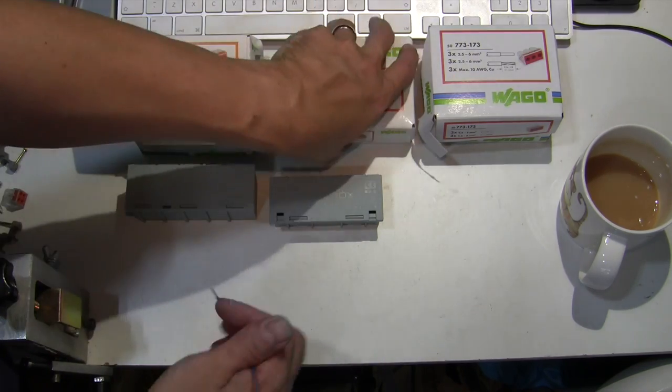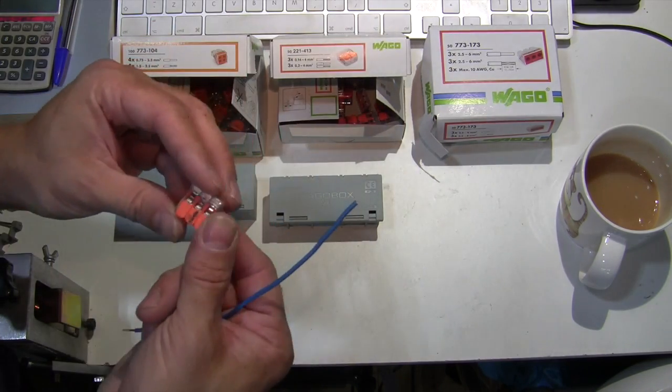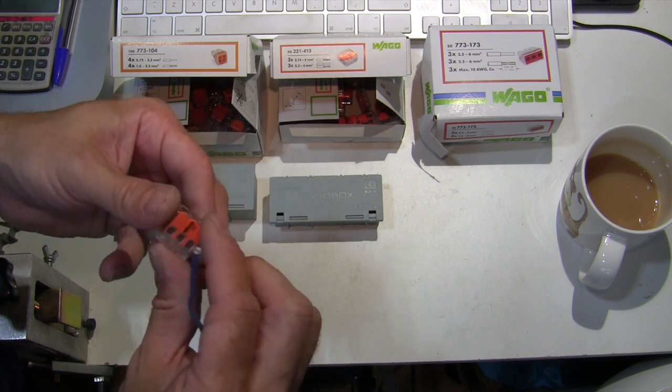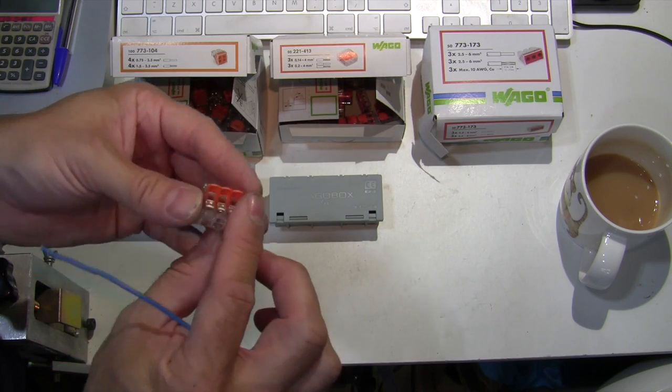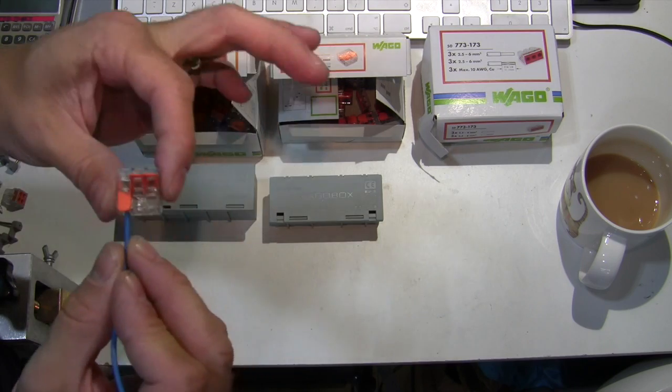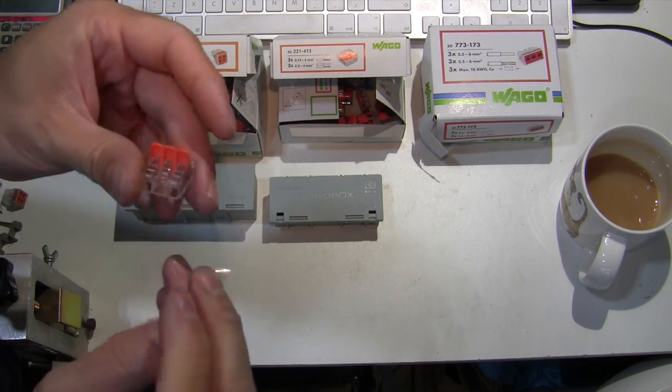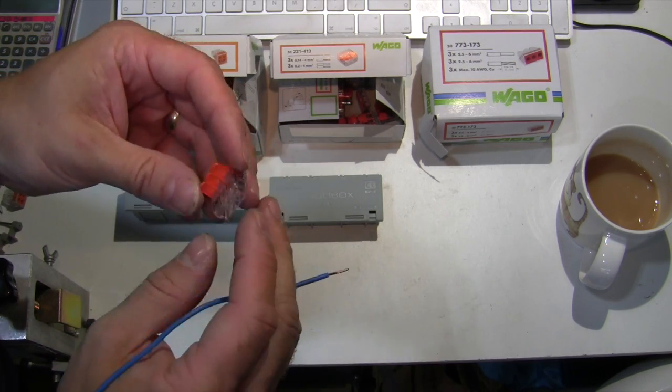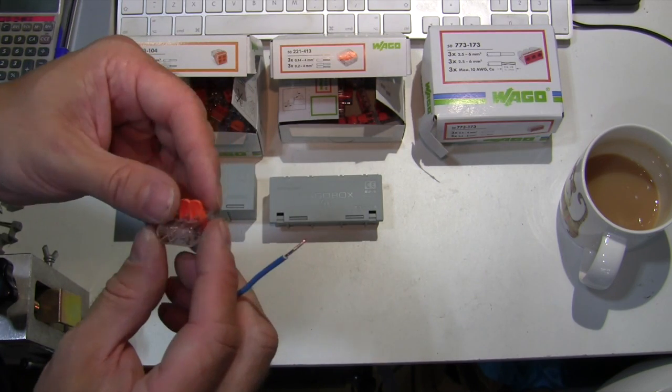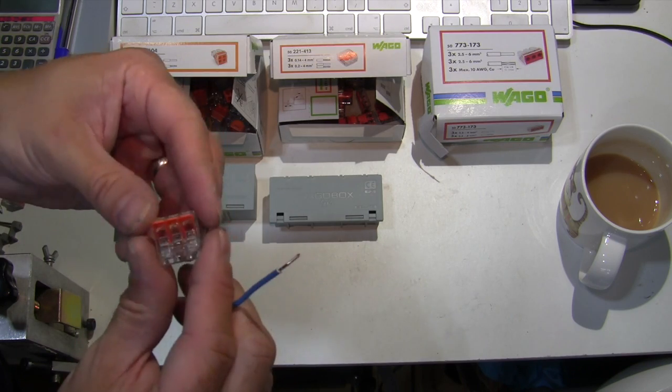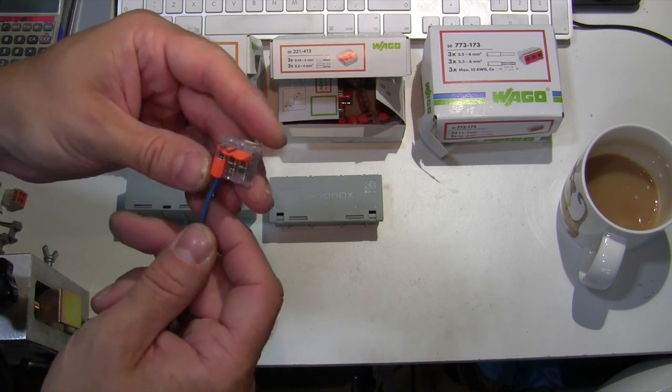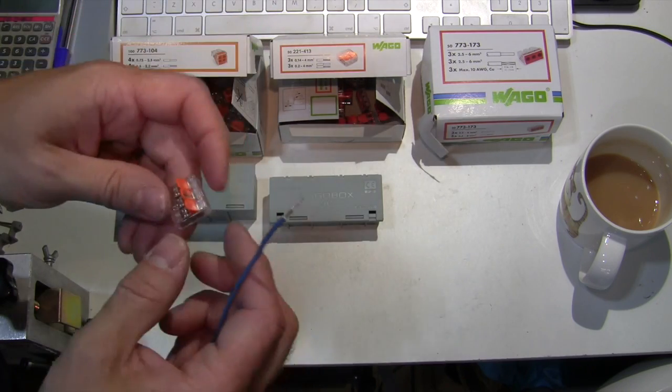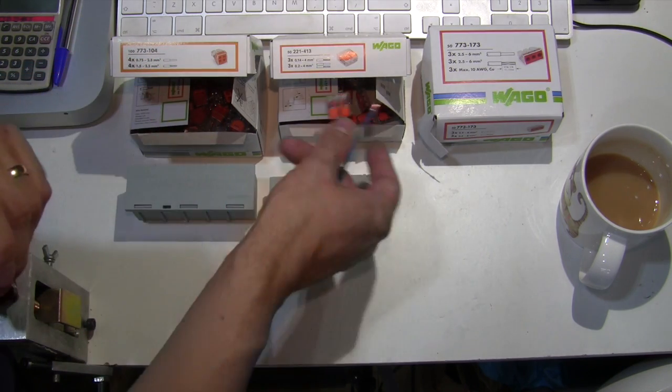And if you don't want to go for that sort of connector, they do a lever type as well. I like the 221 series here, which is the slightly more expensive, but it's the clear finish. So again, you can see this particular one is a three-way and the wire goes in and this time a lever will clamp it down. But it's easily releasable. We tend to use these, for example, somewhere where you want to put in a temporary connection when you're on perhaps a first fix environment and you're doing your dead testing, making sure that everything works. We stick these on, do all our tests, and then we can easily take them off again for when we're ready to put the actual accessories in place.